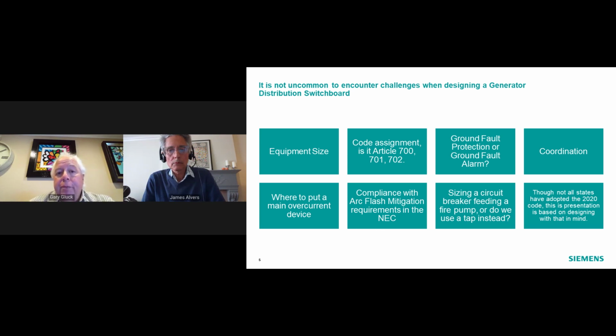Compliance with arc flash mitigation requirements in the NEC, which is 240.87 and 240.67 in the code. It's a little bit counterintuitive because there are some methods of achieving the selective coordination which would, in fact, maybe cause the system to shut down during a fault condition or an arc flash condition. And it's a little bit counterintuitive: do we really want to have compliance with that? But those code sections really don't allow for any exceptions to that. So we'll get into that.